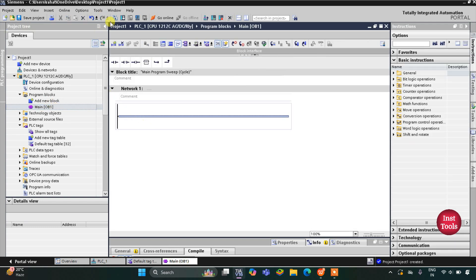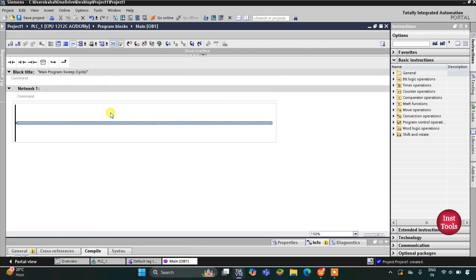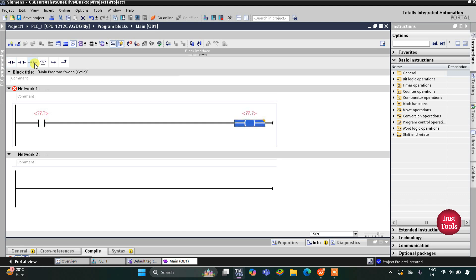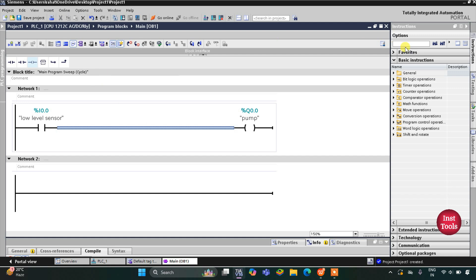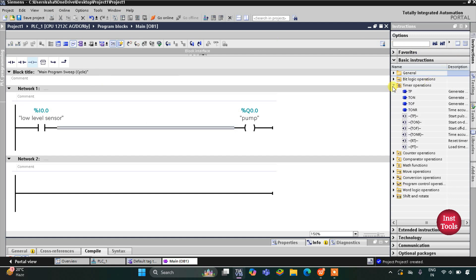Here we will draw the ladder diagram. I'll minimize this and zoom in. Firstly I will insert a normally open contact and then a coil. This normally open contact will be for the low level sensor, so I'll write L and select low level sensor. The coil is for the pump, so I'll write P and select pump from the list. When the low level sensor detects the level is low, the pump will turn on. This pump should turn on only for 20 seconds, so I will insert a timer here — timer operations — and then TP.